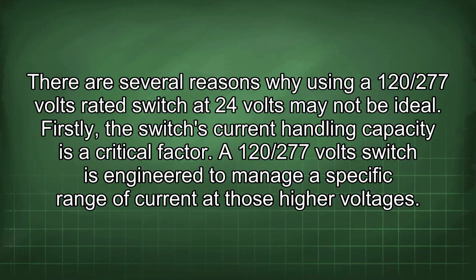There are several reasons why using a 120/277 volts rated switch at 24 volts may not be ideal. Firstly, the switch's current handling capacity is a critical factor. A 120/277 volts switch is engineered to manage a specific range of current at those higher voltages.